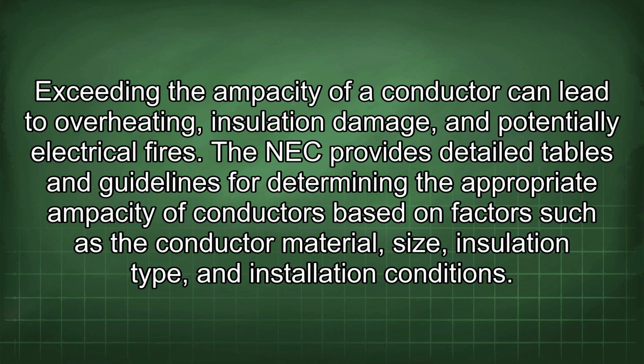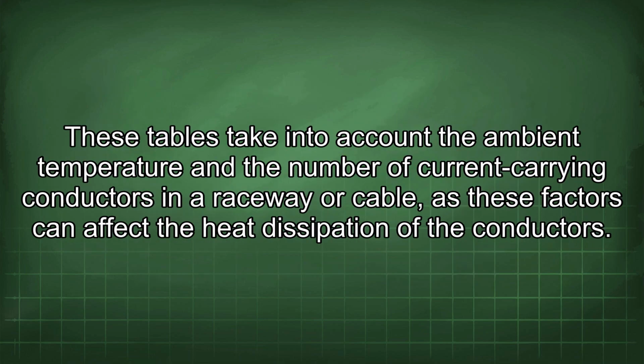The NEC provides detailed tables and guidelines for determining the appropriate ampacity of conductors based on factors such as the conductor material, size, insulation type, and installation conditions. These tables take into account the ambient temperature and the number of current-carrying conductors in a raceway or cable, as these factors can affect the heat dissipation of the conductors.